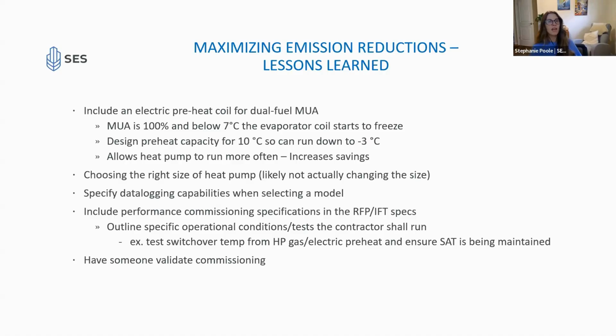So we're validating it. And then the other key learning I'll share is for a dual fuel makeup air unit, because remember, it can't run down quite as low since it's a 100% outdoor air unit. If the goal is to maximize emission reductions, you can put an electric preheat coil before the heat pump. Because around 7 degrees, the evaporator coil starts to freeze when the air outside is less than 7 degrees. That means you can only run your makeup air unit heat pump down to about 7, which is quite a bit higher than a rooftop unit would run to, say -5, -10. If you put an electric preheat coil in there, now all of a sudden you can run it down to maybe -3, which increases the range you can run the heat pump quite a lot and is going to get you more emission reduction overall. Yeah, those are some of the big ones.